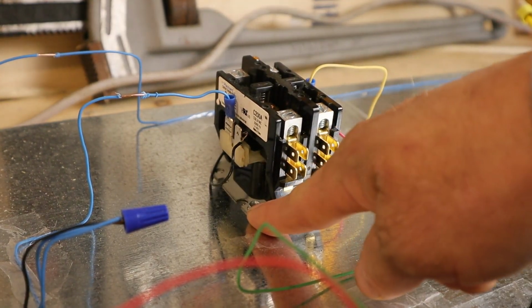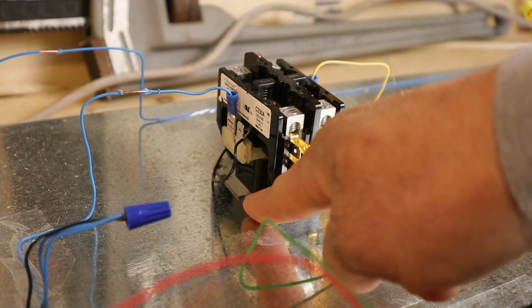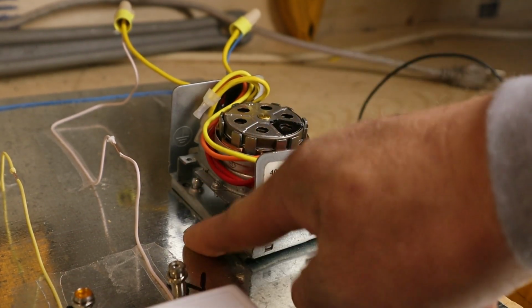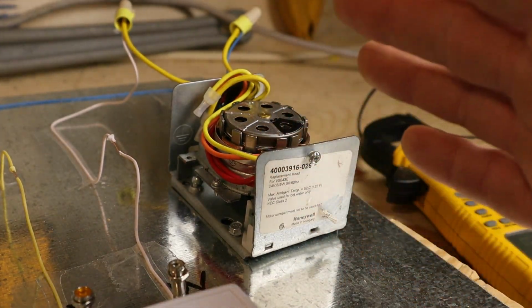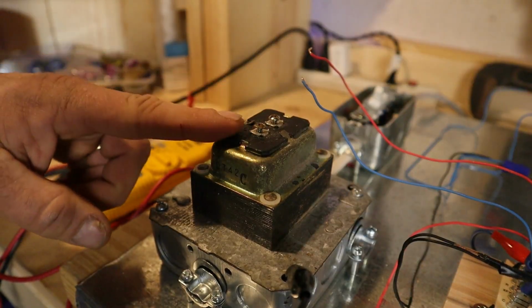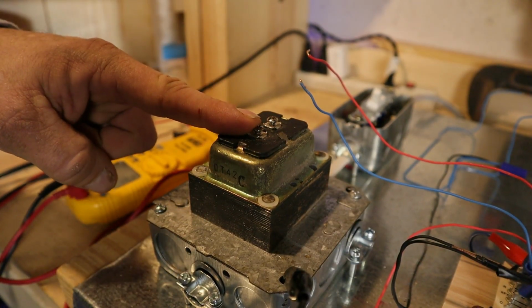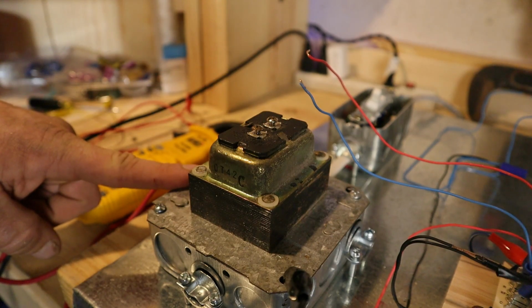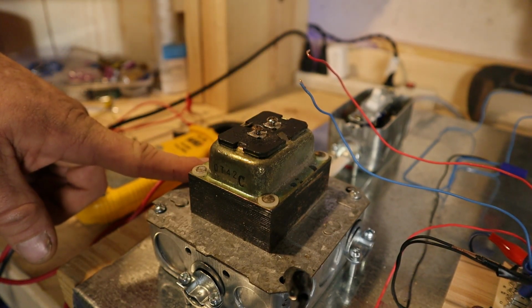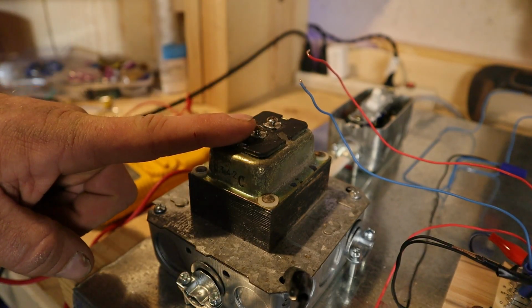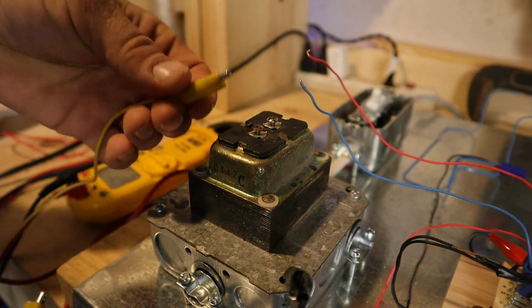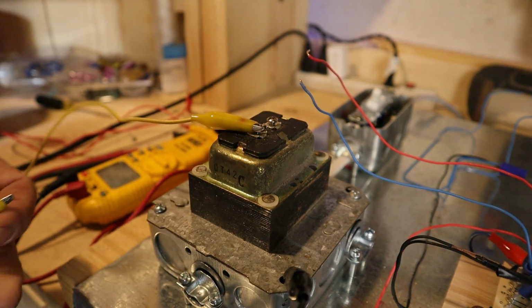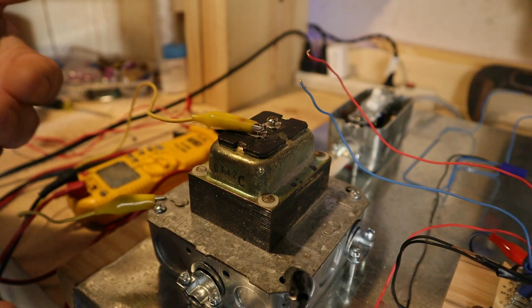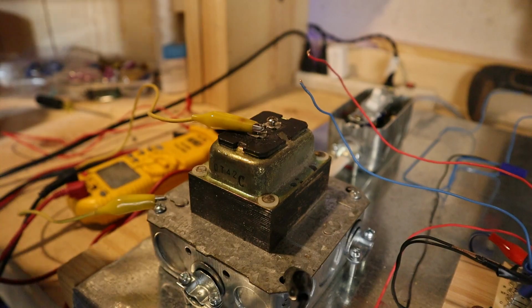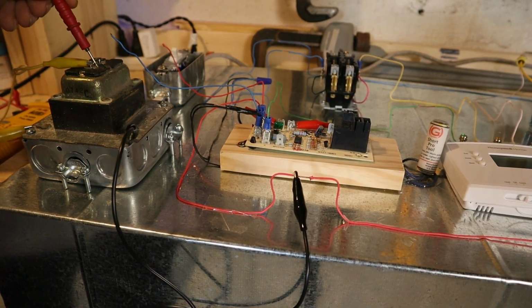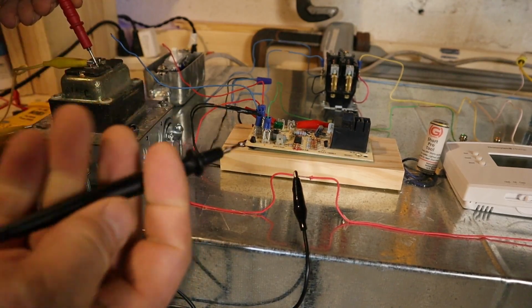In my model here, you can see my contactor has a metal base that is mounted on the sheet metal, so that is also grounded. The metal cover on my zone valve in this model is mounted on the sheet metal, so that is also grounded. So any metal touching metal that is grounded is also going to be grounded. Now a floating secondary has no path between the common on our low voltage circuit and the ground that is going back to the ground on our high voltage circuit. So these are completely separate, and that is why we call it floating. A grounded secondary would essentially be the same thing as me putting an alligator clip on the common and clipping it to metal, and now I will get a continuity reading on any common point in my low voltage circuit and the metal ground. So I have one probe on my common on a transformer, the other one I could touch to metal anywhere and get continuity.